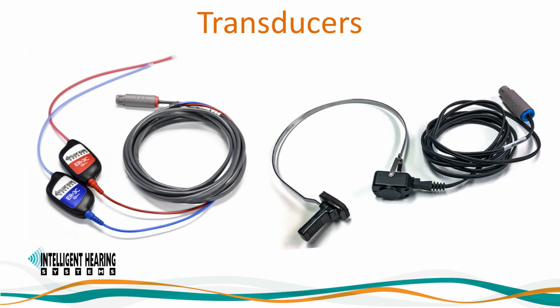Ensure the transducers being used are compatible with the SmartEP and the SmartEP ASSR system. Only transducers supplied by IHS are compatible with IHS devices and will have the proper connector, impedance, and calibration. All IHS devices use 300 ohm ER3 insert earphones and 300 ohm B71 bone conductors. Duet devices with version 1.4 or higher are compatible with the 10 ohm B81 bone conductor. Duet devices with version 1.5 or higher are also compatible with the high-frequency ER2 insert earphone.